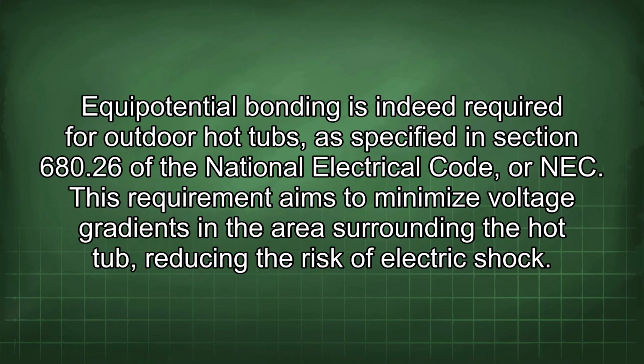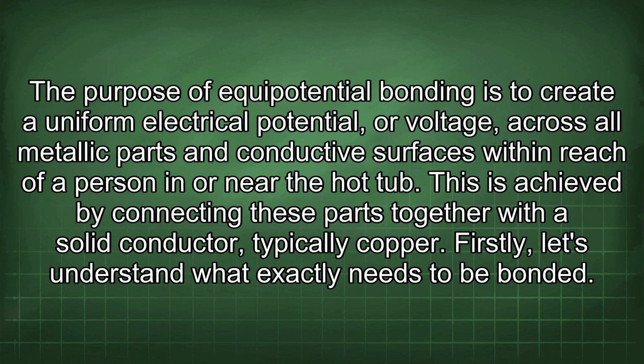Equipotential bonding is indeed required for outdoor hot tubs, as specified in Section 680.26 of the National Electrical Code, or NEC. This requirement aims to minimize voltage gradients in the areas surrounding the hot tub, reducing the risk of electric shock. The purpose of equipotential bonding is to create a uniform electrical potential, or voltage, across all metallic parts and conductive surfaces within reach of a person in or near the hot tub. This is achieved by connecting these parts together with a solid conductor, typically copper.